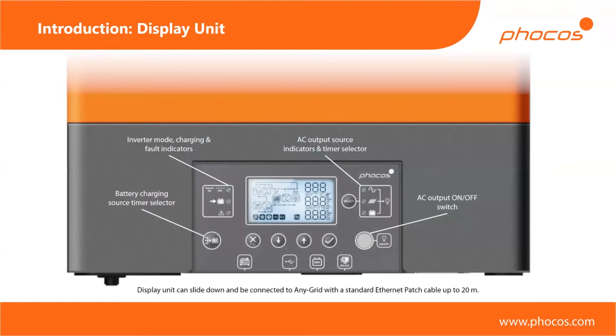Here you can see a picture of the display unit. So again, this is removable. On the left here, you can see a battery charging source selector for the timer. So you can set up a basic priority scheme. You'll see later what that means. And then you can override that with this button for a certain number of hours per day. Then we have various LED indications, so you can see if the device is currently running in grid or off-grid mode. You can see if it's charging, and you can also see if there's an error, for example.